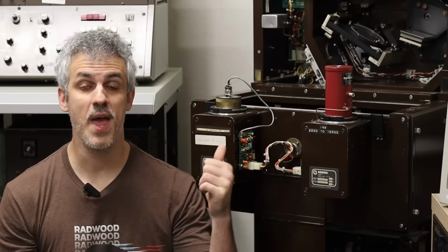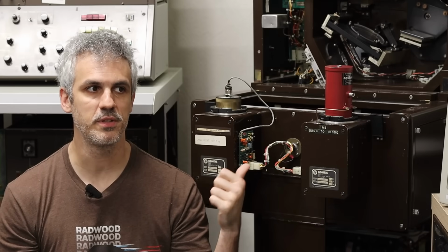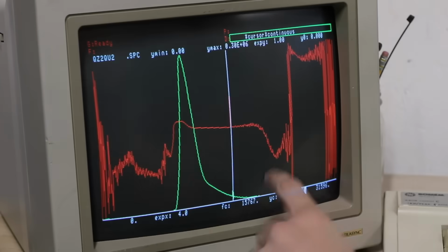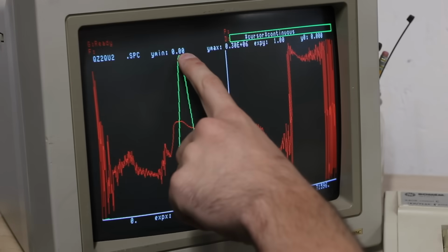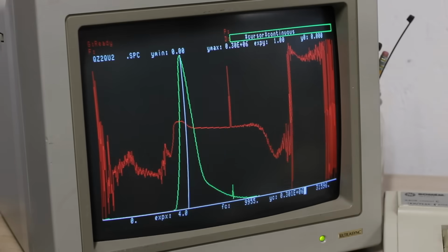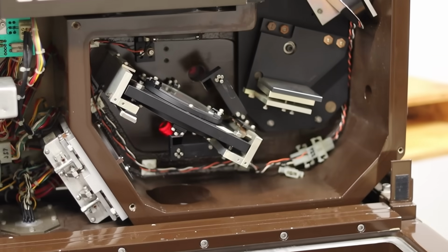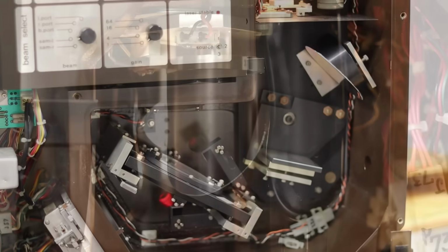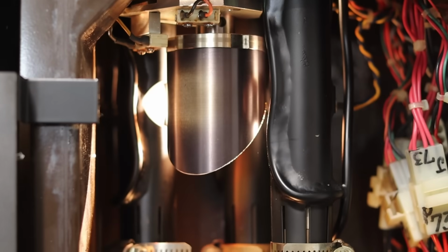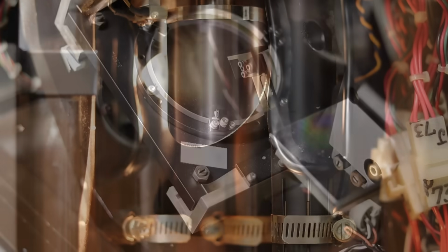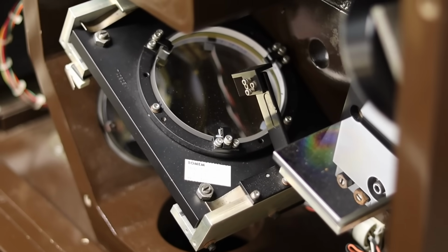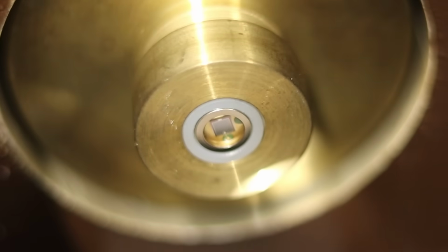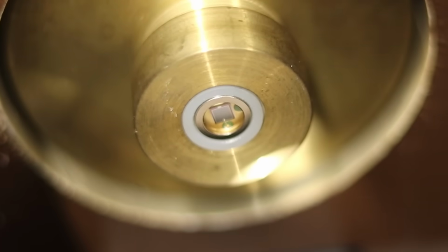Now, like I said, normally you would have a sample in the sample compartment, but there's nothing stopping us from just not putting anything in there. And then if we take a spectrum like that, it really just gives us information about the atmosphere around us. And that can tell us some interesting things, but mostly what it can tell us are the capabilities of the machine. We can see exactly which wavelengths of light that source up top is putting out. We can see the limitations of the beam splitter in the middle. And most importantly for today, we can actually see what wavelengths the detector can detect.